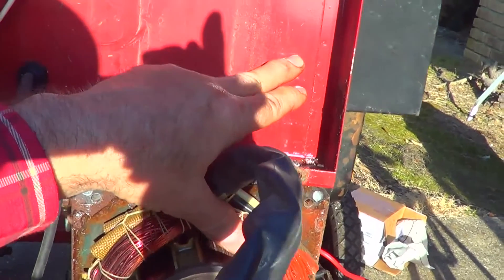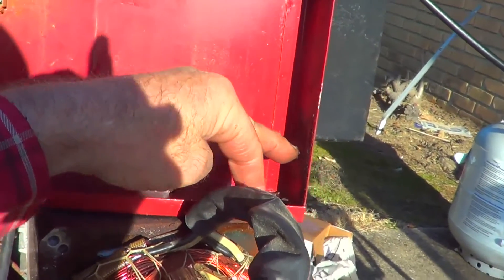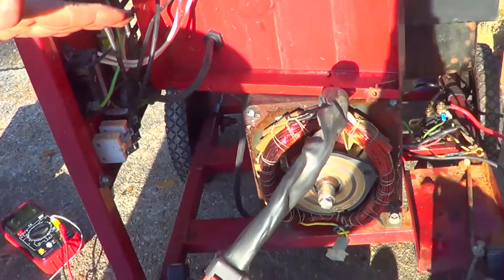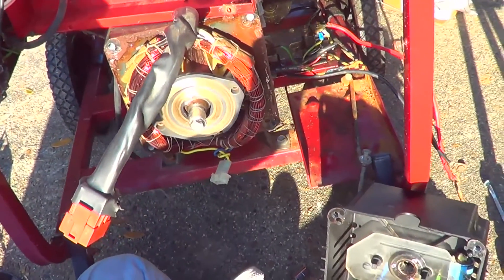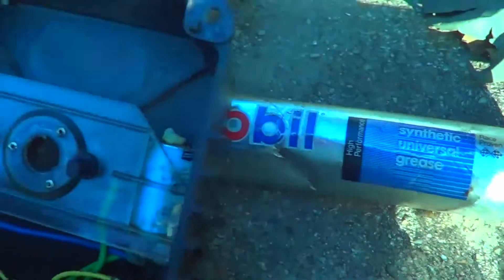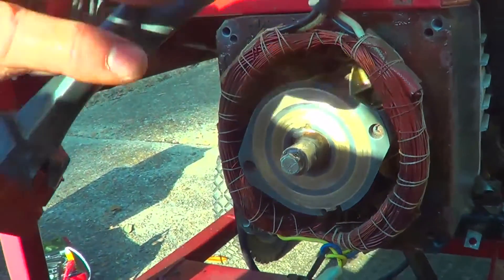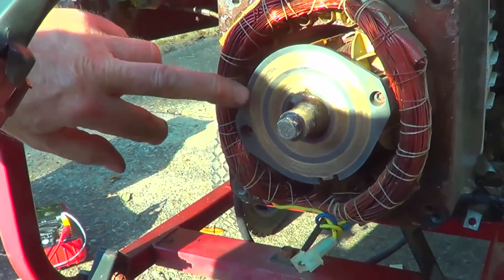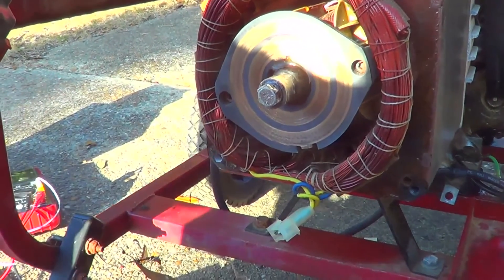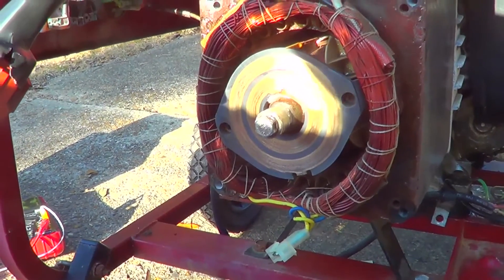You can see the scum line from floodwater — it at least got up to here. There's some crap under here, so it probably went up at least as high as here on the generator. We put some Mobil synthetic grease, just a little bit on the inside of the bearing. We're going to put this back on the stator. I went ahead and sanded this a little bit to get some of the corrosion off.